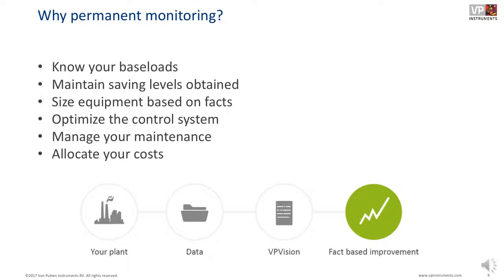Size the equipment based on the facts. So when you're thinking about expansion, you're going to add a new production facility to the already existing location. You're going to add production lines. You now have something to go back on and look at the data and say, okay, this machine is using on an average so much. So if you're going to duplicate this machine, we need about this amount of air. Is my current set of compressors capable of delivering that? Or should we size up?